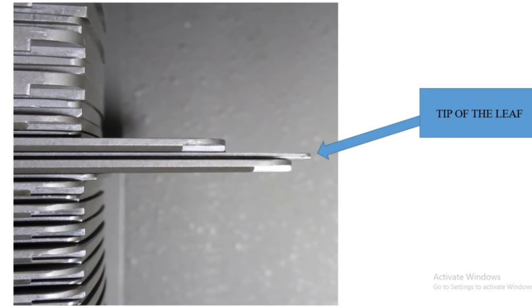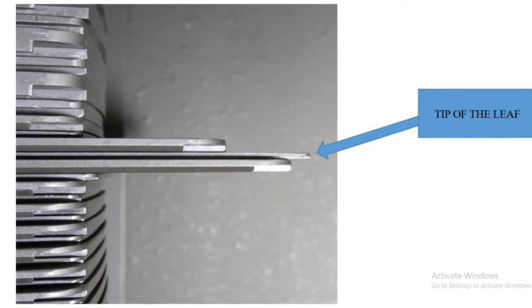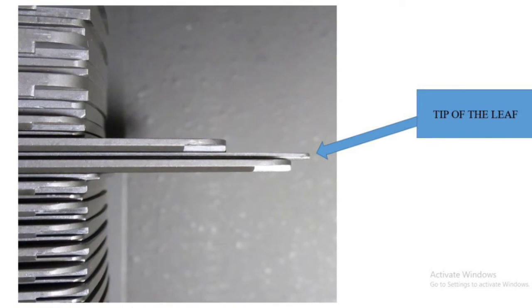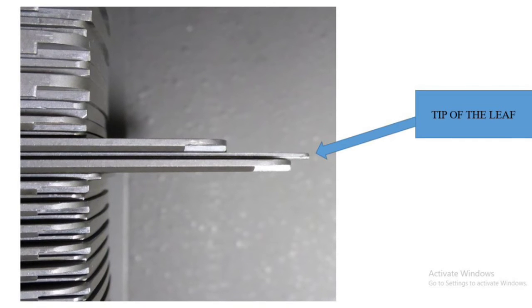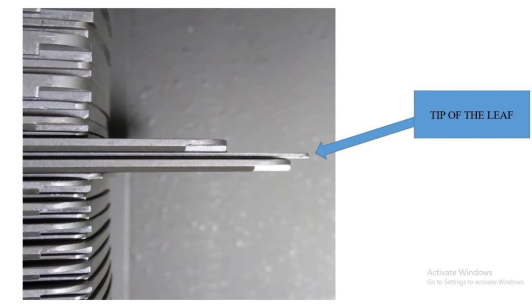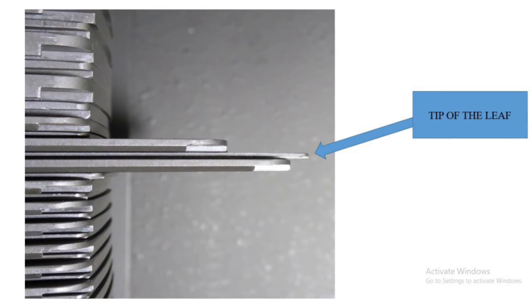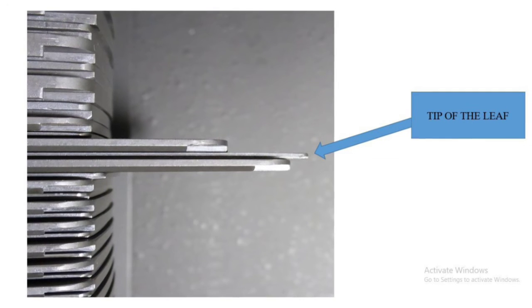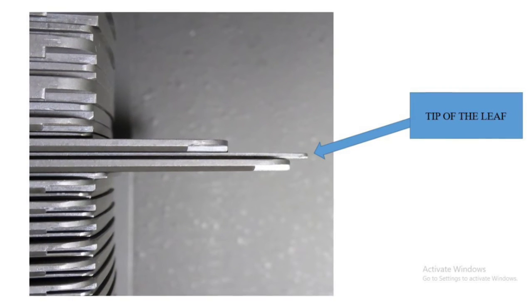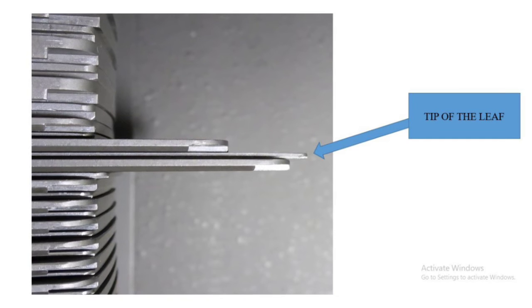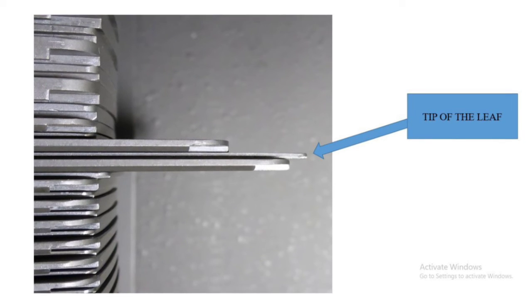Once removed, replace the T-nut and put back the MLC in the same slot of the carriage, and then fix the actuator. Now you have to fix the soft part and try to manually move the MLC, and it should work. Then do the calibration, save the new values and then perform the MLC auto cycle.